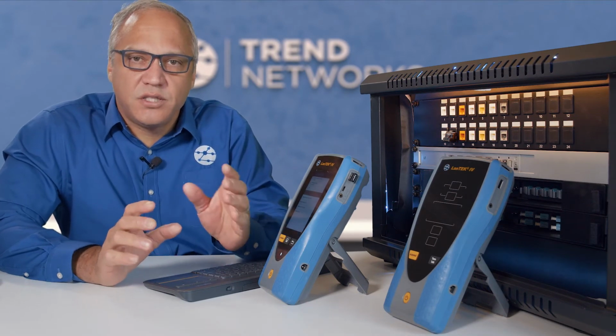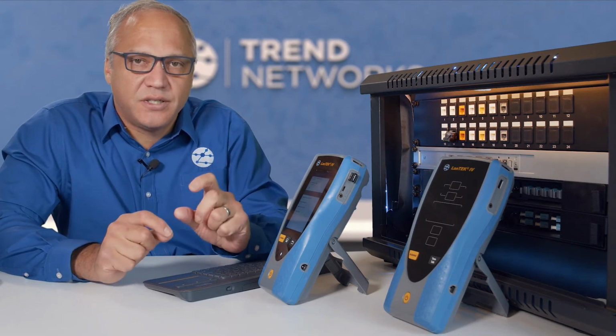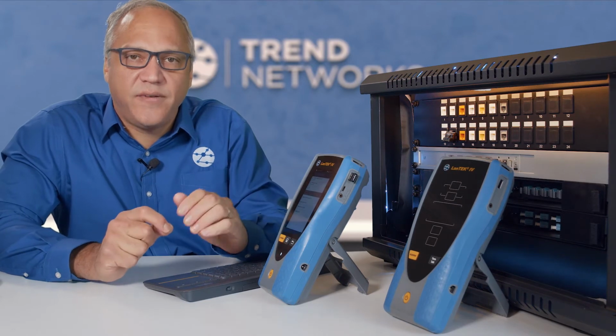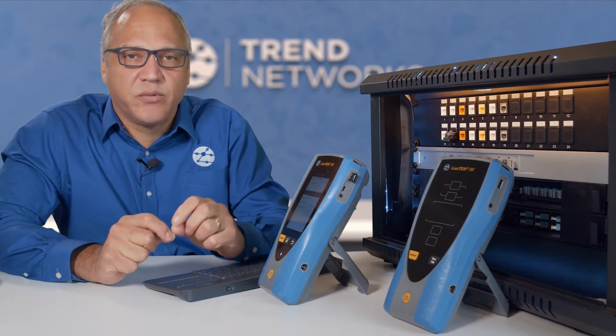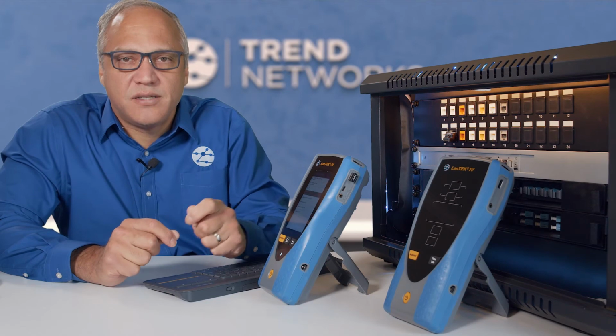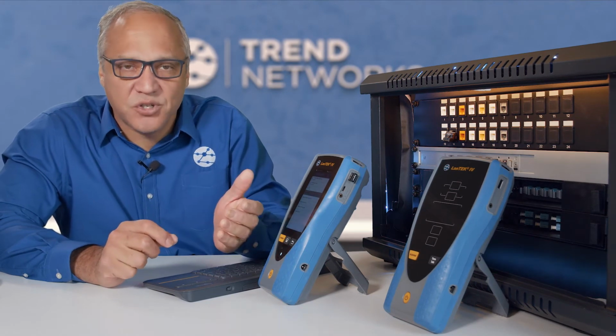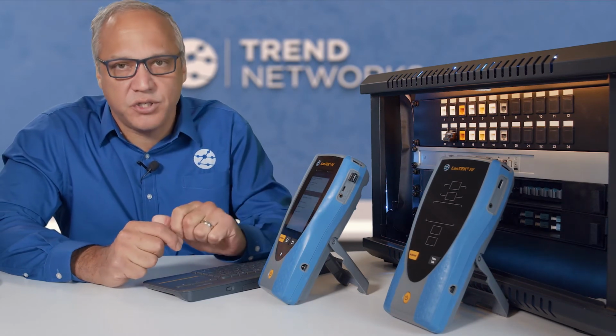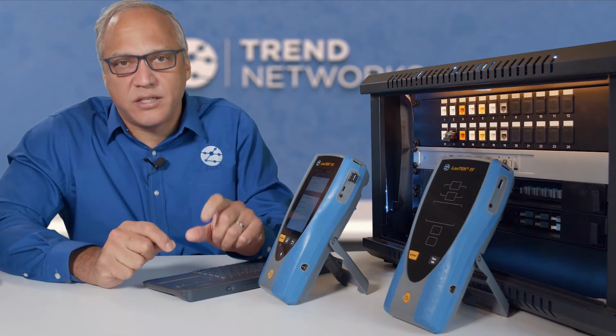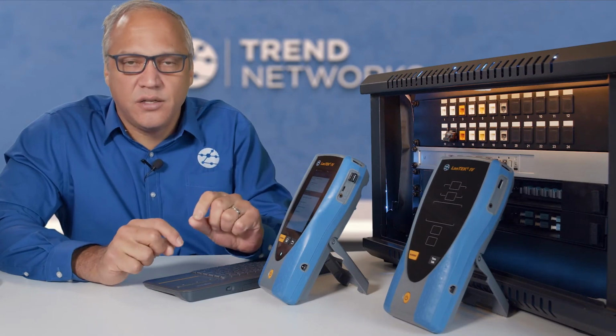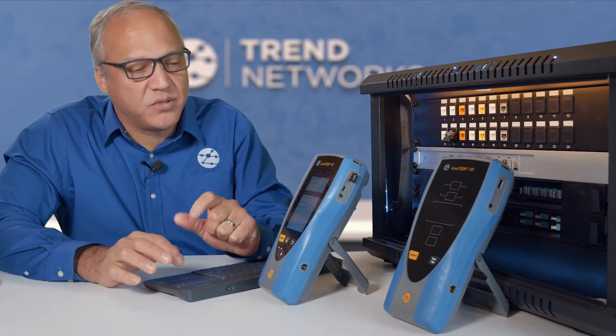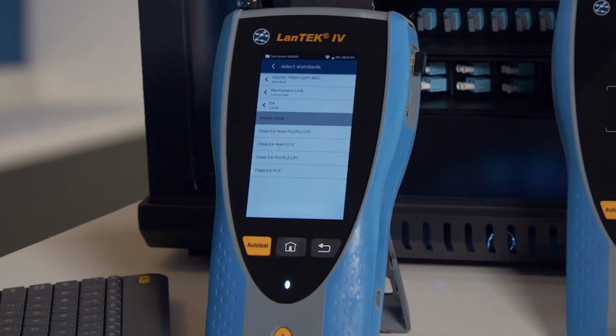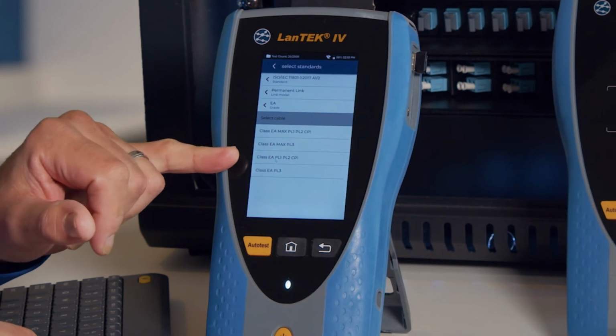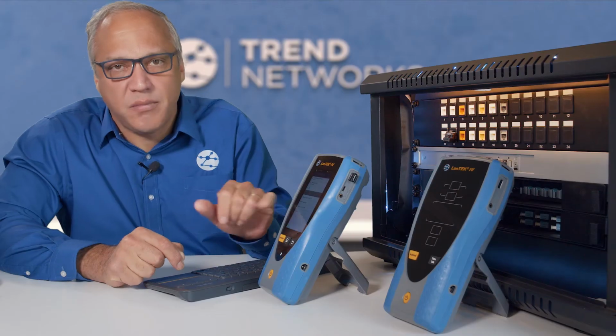So beyond just the basic minimum test, we're also going to test and do a pass-fail measurement for things like DC resistance unbalance, TCL, and ELTCL, which are optional for Class EA. But in this case, if we choose max, it's telling the tester, I want to measure those and do a pass-fail result on them. So that may be a requirement. If we don't need that, the standard test would just be the same measurement without the max.